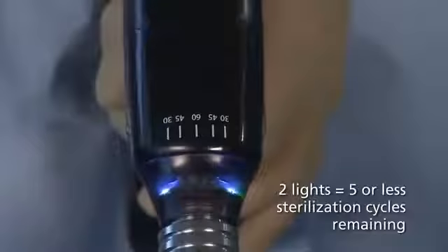If 2 white lights appear, then there are 5 or less procedures left on the adapter before end of life will be reached. In this situation, press and hold both the open and close fire button simultaneously. The white firing progress indicator lights will flash once for each remaining sterilization cycle left on the adapter. This sequence will continue as long as both buttons are held.